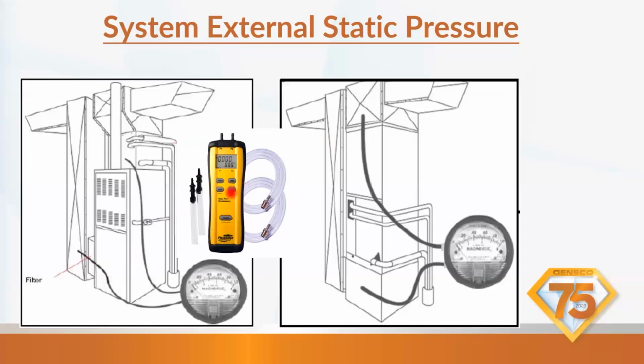You're going to have to take gas pressures too. So this is a dual port where you can get the supply and the return. You're going to remove this filter if that's the case, because you don't want any filter. We want about 0.5 static. That's the design pressure of the gas furnaces and the air handlers.